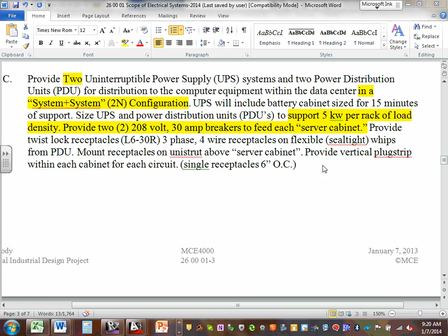So, whips from the PDU mount receptacles on the unistrut above the server cabinet. There's going to be a vertical plug strip within each cabinet also. So those 2 receptacles are above or under the floor, depending on the situation, and the plug strips plug into those. It's not that far from a plug strip like this. They're a little bit fancier, sometimes they're metered, but they're vertical and like 42 RU. They're 6 feet tall, and they just mount to the side of the rack. And that's where your server is going to plug in. There's probably anywhere from 10 to 30 plugs on each plug strip, and the stuff that's in the rack plugs into that. So that's the vertical plug strip of each cabinet.